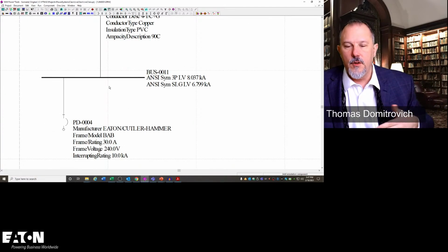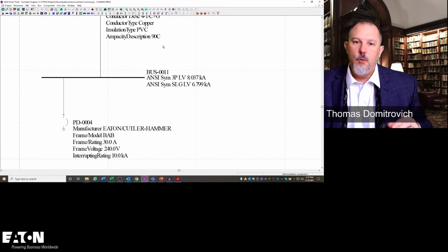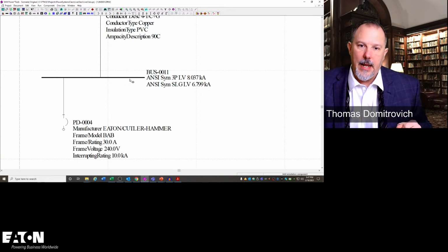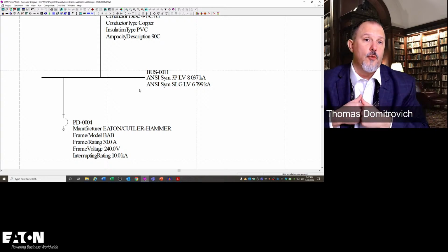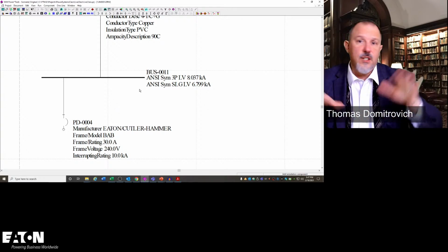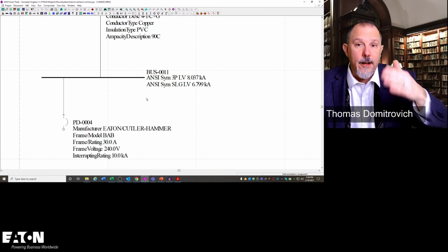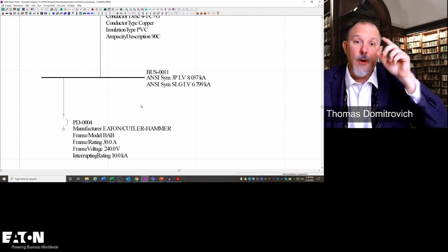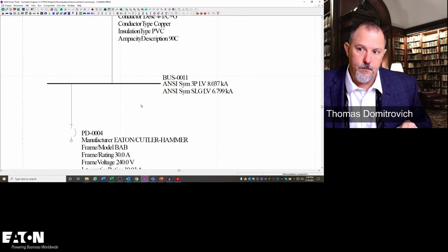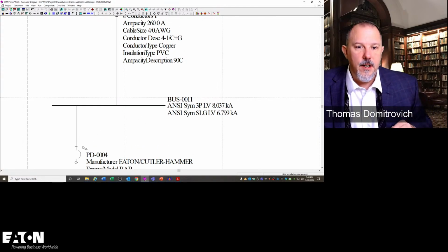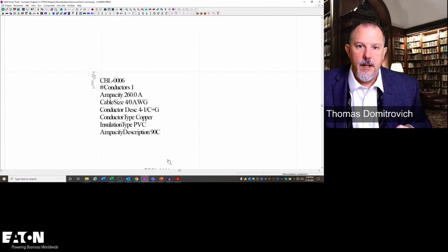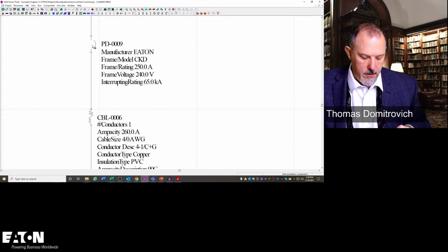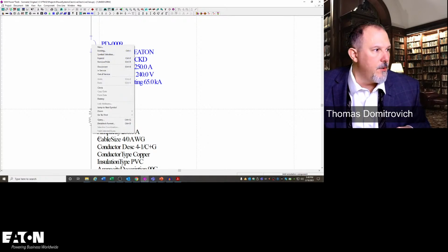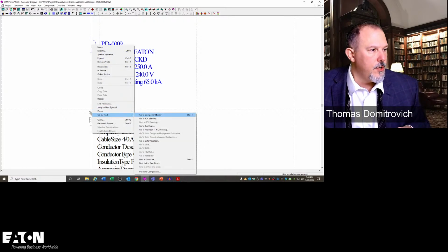If you're doing a full-blown study, you would have a lot more breakers on each of these buses, because you'll be doing load flow studies. You'll be doing short circuit studies throughout the power distribution system. So I'm not showing other breakers in this, but there would be other breakers on this panel. So I would pick this breaker, and then I would pick this breaker, and I would send those to a TCC drawing, and I'll call this level 1.